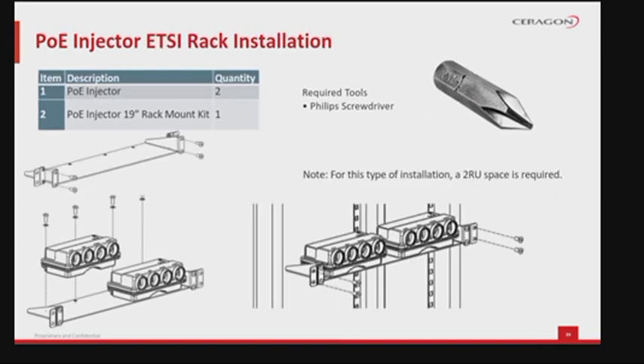To mount the PoE injector to an ETSI rack: 1. Mount the PoE injector to an ETSI rack using a 19-inch rack adapter and ETSI adapting ears. 2. Connect the ETSI adapting ears to a 19-inch rack adapter using 4 M6 screws. 3. Mount the PoE injector on the adapter through the wall mounting holes using M6 screws and washers. 4. Mount the 19-inch rack adapter with the ETSI ears on the ETSI rack using 4 M6 screws and cage nuts. Please note that for this type of installation, a 2-rack unit space is required.